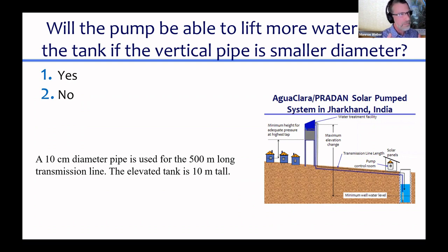So what actually makes it hard for the pump? The pump is experiencing pressure. And where's the pressure coming from? There are 2 things that cause the pump to experience pressure. One is the hydrostatic head, which is basically the elevation of the water where it's entering into the water treatment plant at the top of that building relative to the level in the well.